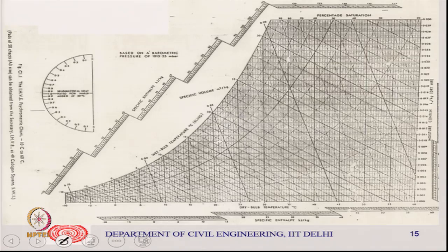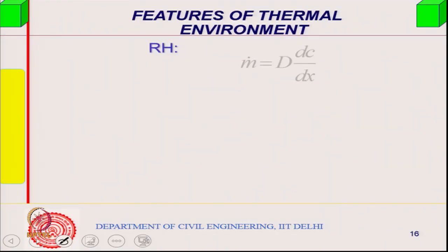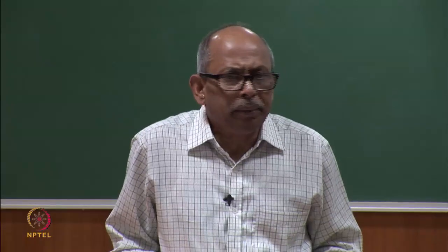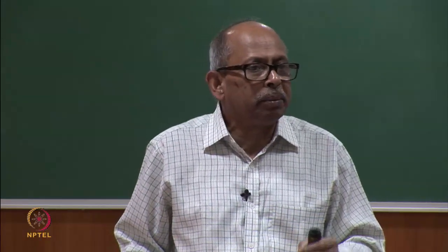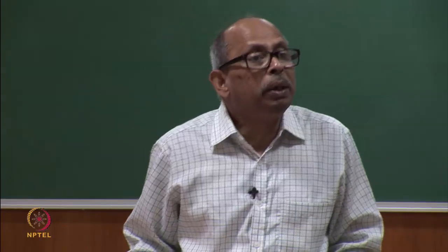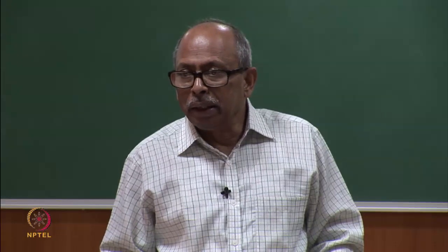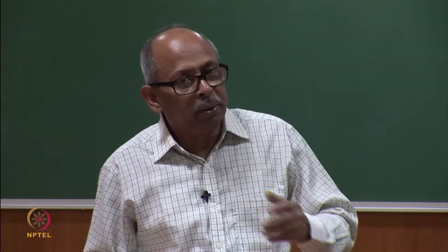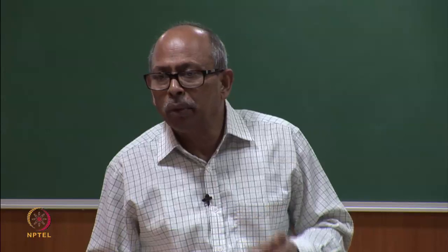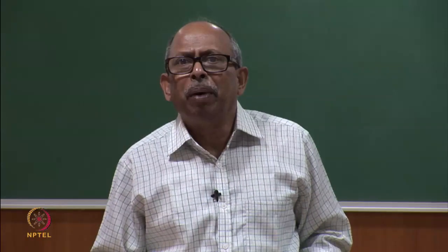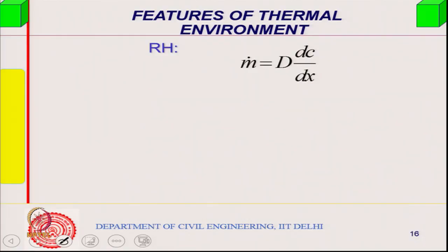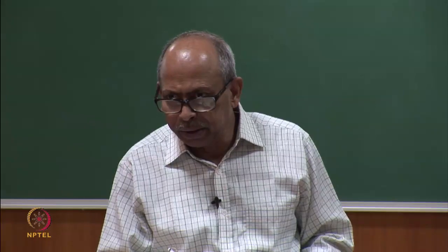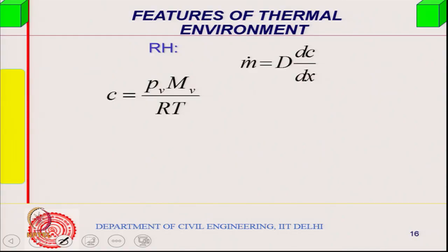Okay. The psychrometric chart I have already talked about, and one may look a little into the equation of dew point, because if you want to estimate how much condensation, or the temperature corresponding to the moisture content at dew point for a given condition, you would like to reduce the moisture content. You would like to have knowledge of dew point as well as wet bulb depression. Some of them, for example, calculating the relative humidity I just mentioned earlier. Then for dew point there are some empirical formulae.